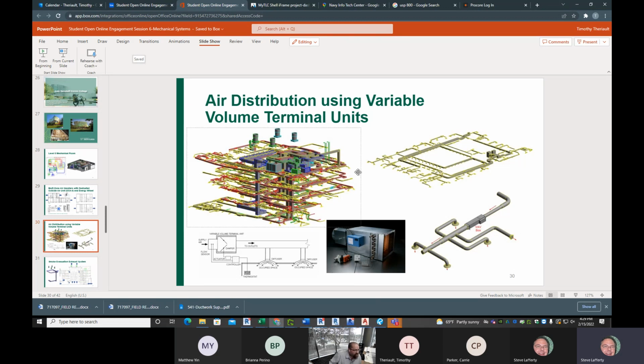So I went ahead and took that level down and isolated one floor. And this is just the supply on one floor. It comes down and it spreads out to the floor. There's a whole bunch of classrooms and tons of other rooms that want to be controlled separately from each other. This guy wants to be different from that guy, for each little classroom that's there. So how we do that, I brought it down one more level. This would go to one classroom. This is actually this piece right here, I believe I pulled out.